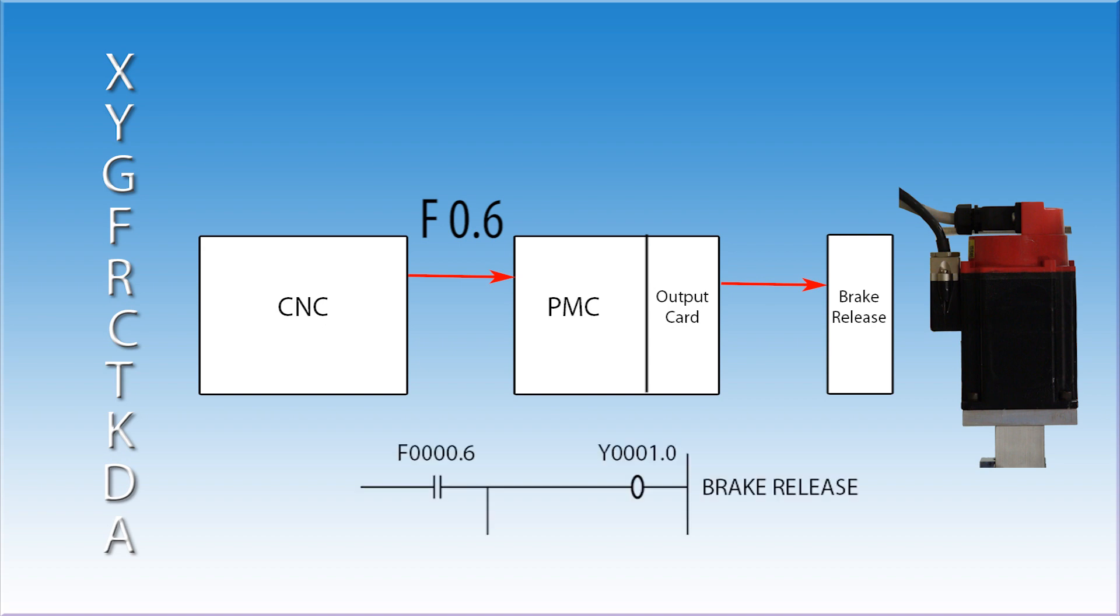F0.6 would be a contact on a rung in the ladder. When this bit goes high, a Y value output will be turned on. This will send out a signal to release the brake. If for any reason the CNC turns the servos off, F0.6 will go low and the brake will clamp. F addresses, like the X addresses, can only be used as an input. FANUC assigns all G and F addresses.